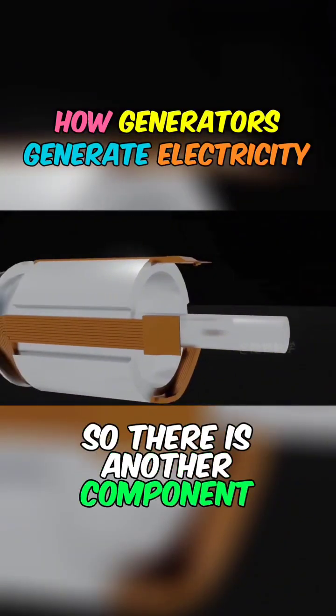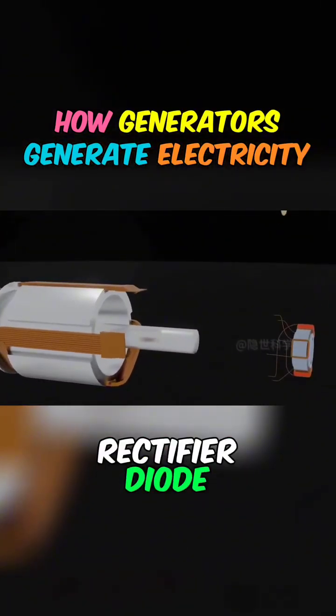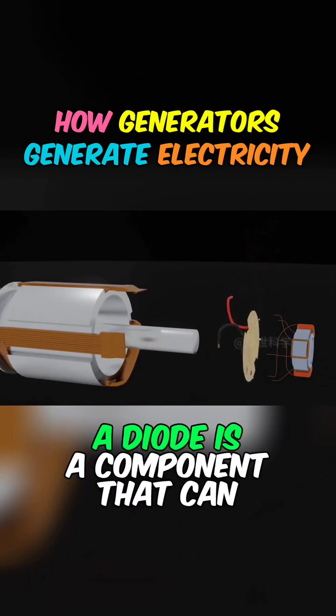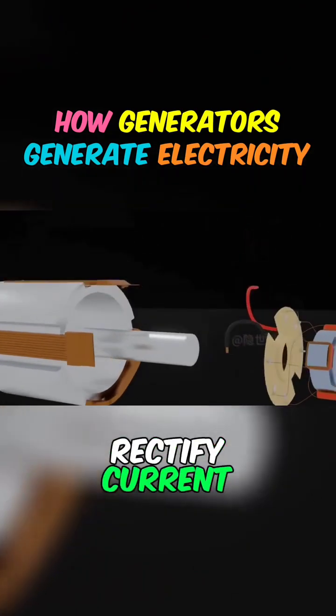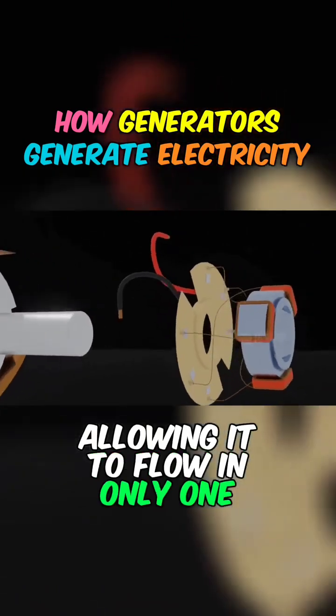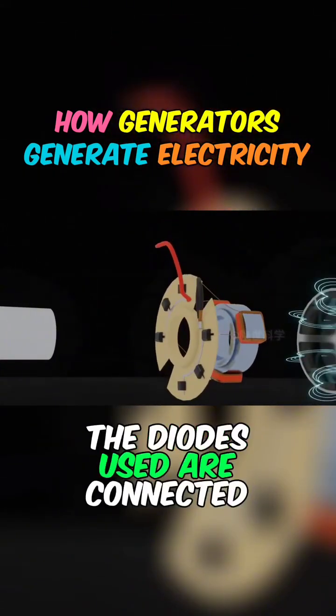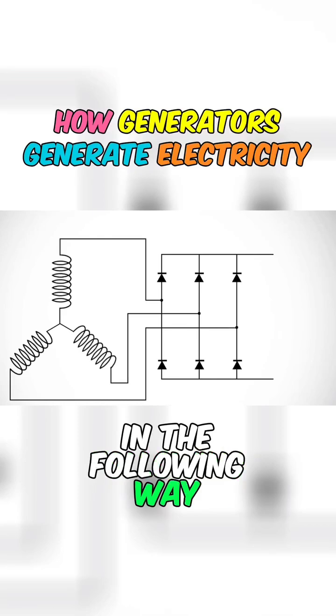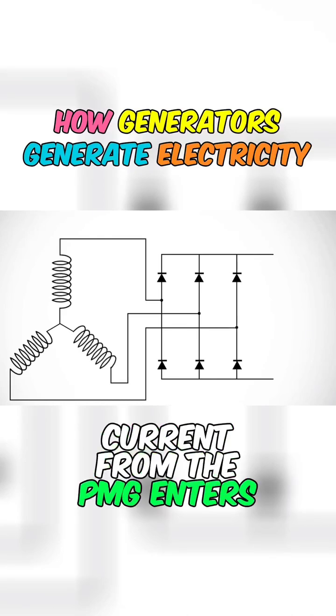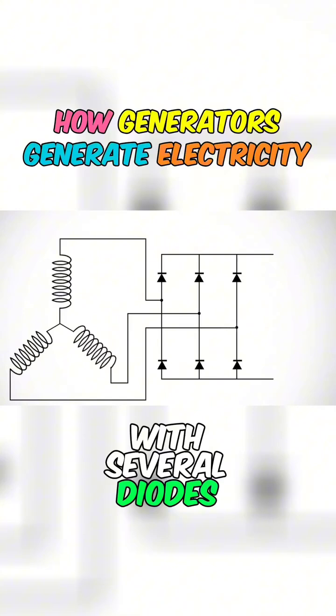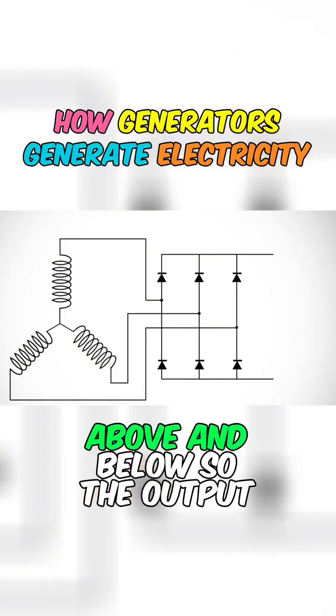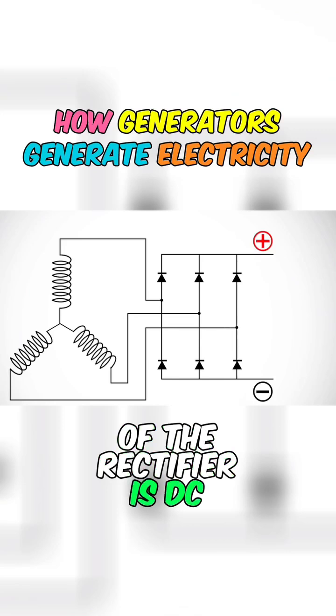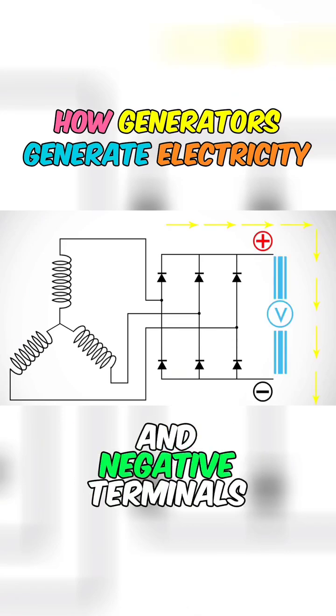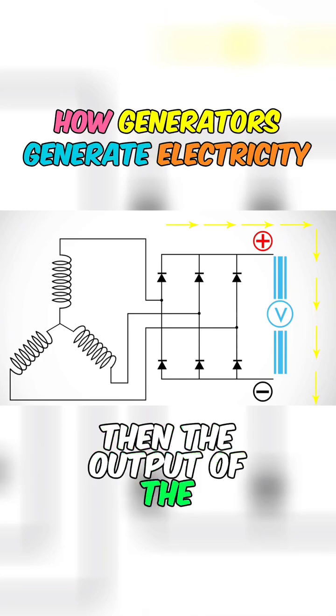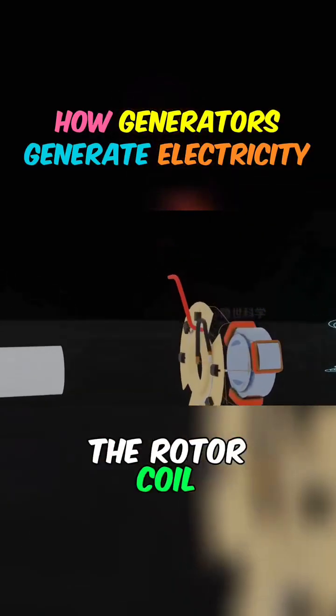So there is another component: the rectifier diode. A diode is a component that can rectify current, allowing it to flow in only one direction. The diodes used are connected in the following way. Current from the PMG enters from the middle, with several diodes installed in the same direction above and below. So the output of the rectifier is DC transmitted through the positive and negative terminals. Then the output of the rectifier is transmitted to the rotor coil.